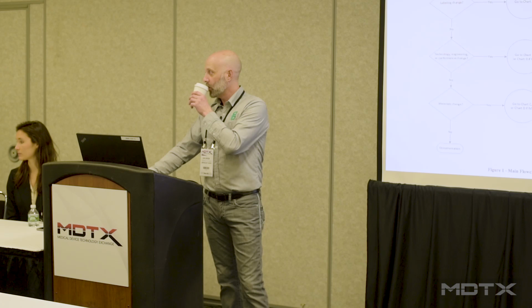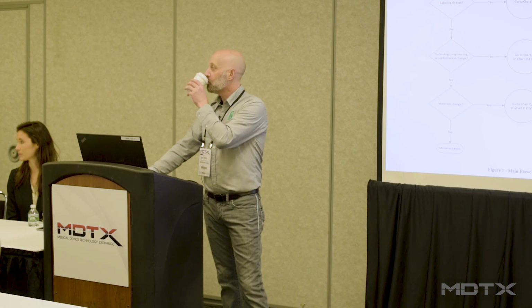So I'm just going to add a couple things. I would echo what John said. I would much rather have a discussion with an FDA reviewer about a difference of opinion as to how I answered one of those triangles than not having any documentation whatsoever on a design change. Risk of FDA inspection, but also strategics and partners, they're going to be giving you just as much of an inspection as FDA does, and they're going to want to see this so that they don't inherit the risks that you've accumulated.